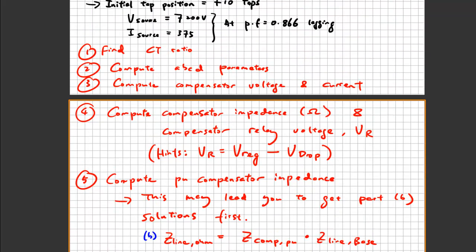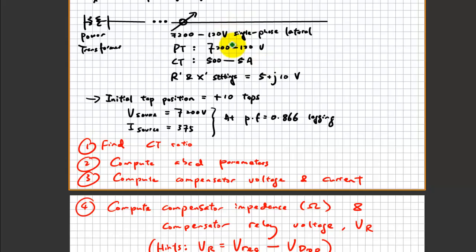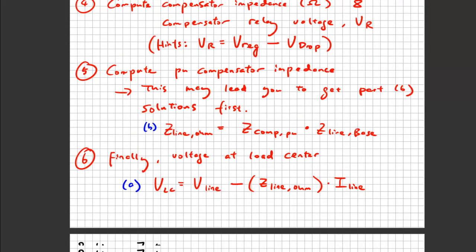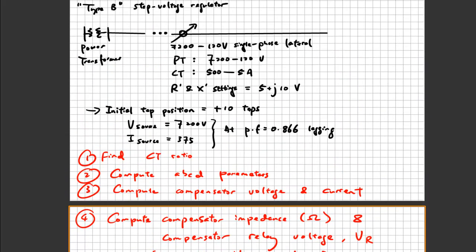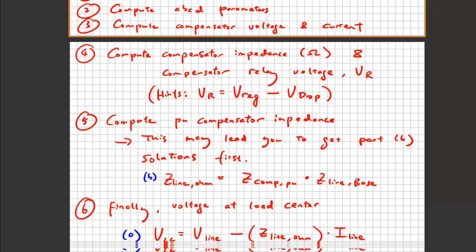Once you find Z_line in ohm units, you can easily find the voltage at the load center: V_load_center equals V_line minus V_impedance, where V_impedance comes from the line impedance multiplied by the line current. That lets you solve two parts of this problem right away. It's a procedural process you have to go through based on any current condition. The final step you can predict is finding what tap adjustments are needed based on the current tap position — if this is tap plus 10, you determine what adjustments are required.